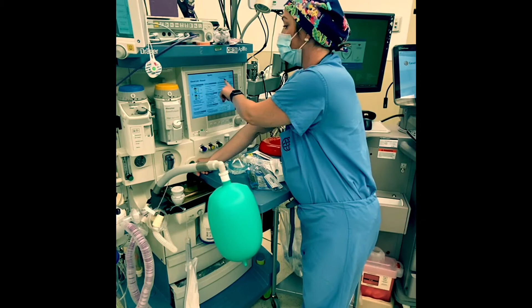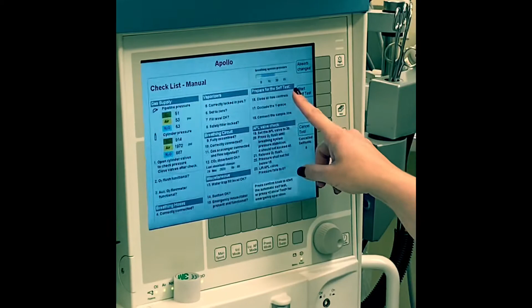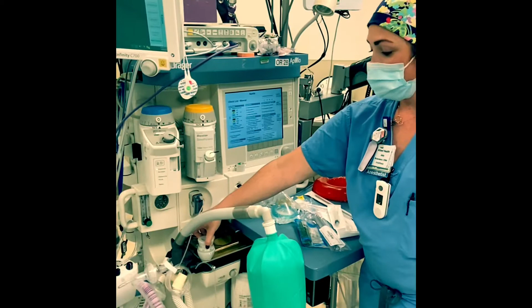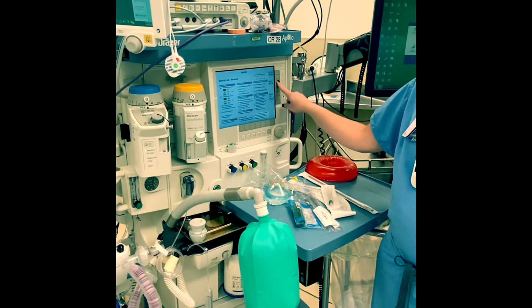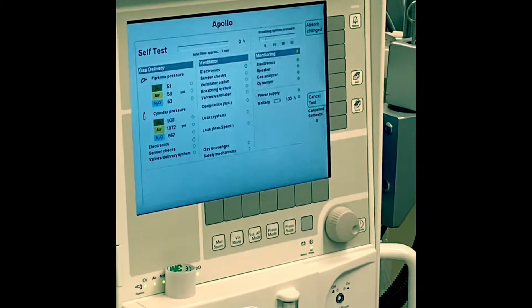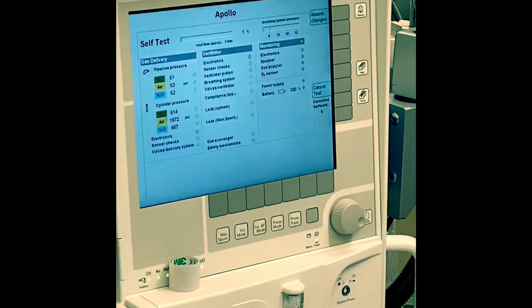And then once your breathing pressure is over 30, you're going to let it go and make sure that it holds pressure, that it never goes above 45 and never falls below 15. So then you're going to lift your APL, make sure that your bag completely deflates, and you're going to leave that APL at 30. After that, you're going to hit this button that says Start Self-Test, and then the machine itself is going to do a circuit test to check the pressure.